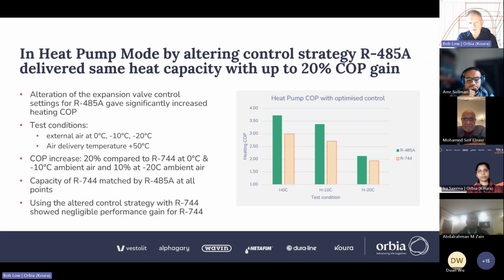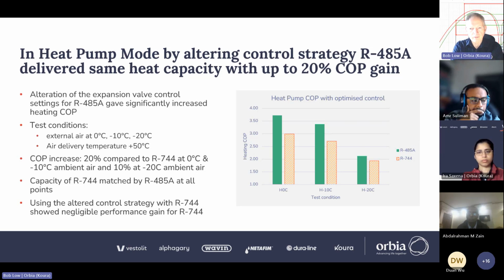Quite an arduous heat pump cycle, air delivery at 50C with a cross-flow heat exchanger, and external air at -20C. That makes a really quite a large pressure ratio even for CO2. And so we're pleased with the performance. This is certainly better than you get with fluorocarbon refrigerant over the same sort of temperature lift. This COP of 3.3 or something like that at -10C ambient is really very good.